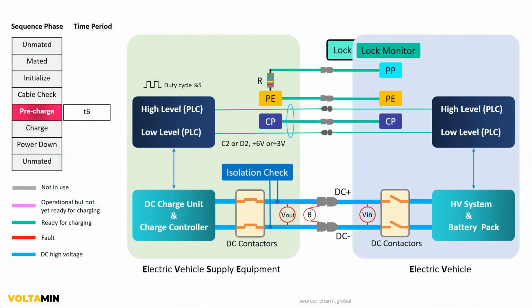At T6, DC supply adapts; the DC output voltage stays within tolerances and the current is limited to a maximum value of 2 A. In the pre-charge phase T7, the EV ensures proper voltage alignment before initiating high current charging. The EV monitors the difference between the EVSE output voltage VOUT and its battery voltage VIN. Once this deviation is less than 20 volts, the EV commands its internal disconnecting device, e.g. DC contactor, to close, establishing a direct electrical connection.